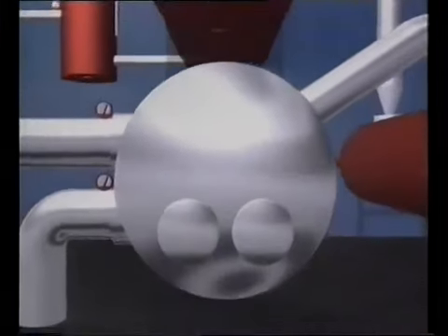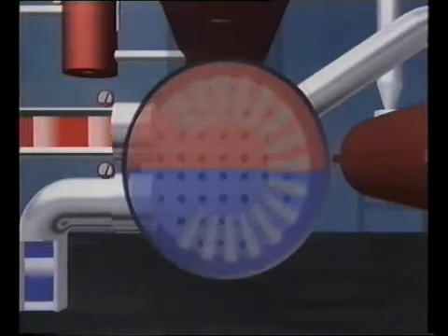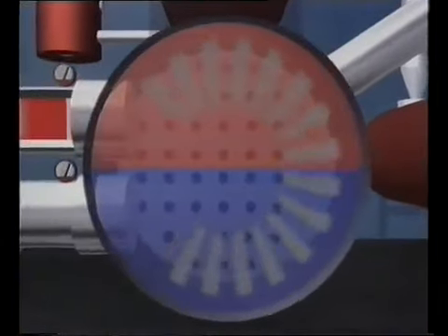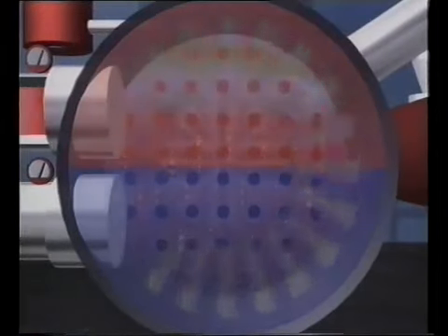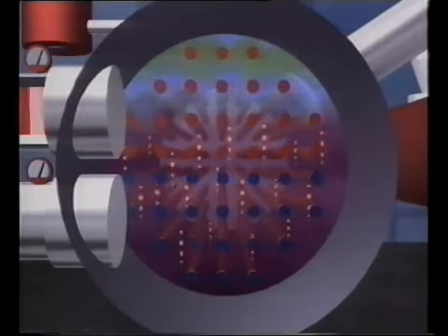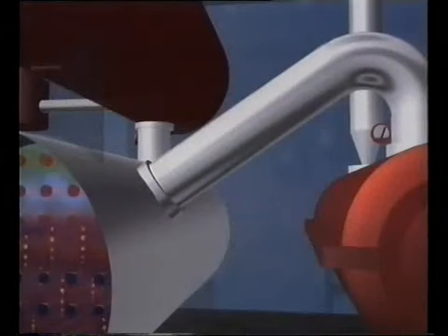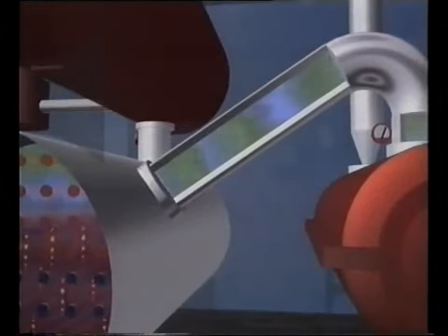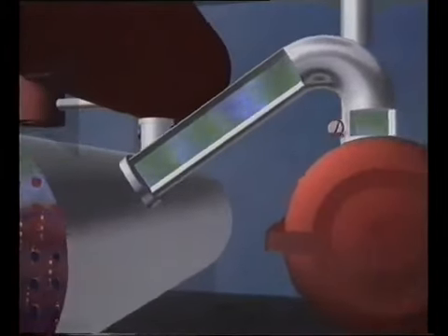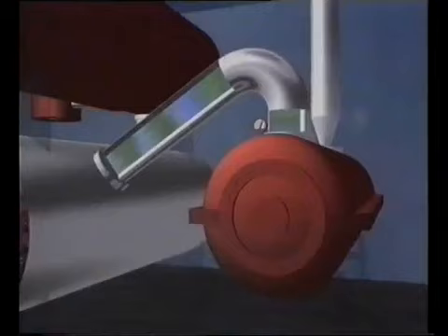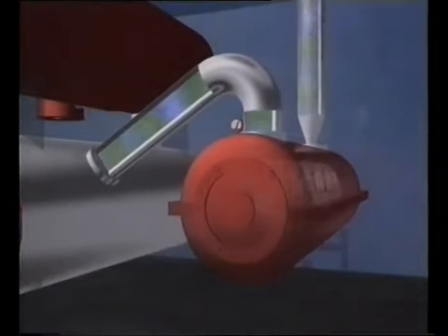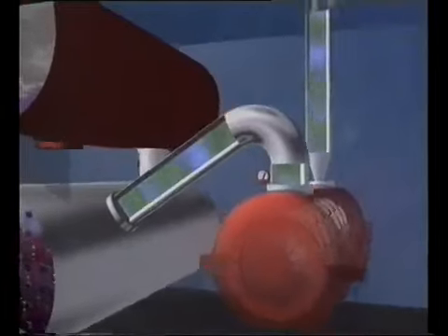A volatile liquid flows into an evaporator, where it acts as a refrigerant, circulating around copper tubing containing the warm water. This causes the refrigerant to vaporize by extracting the heat from the water through the copper and cooling it. Now in gas form, the warmed refrigerant is drawn into a centrifugal compressor, where its pressure is raised, which in turn greatly increases its temperature.